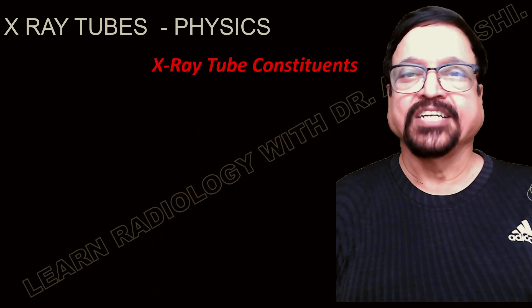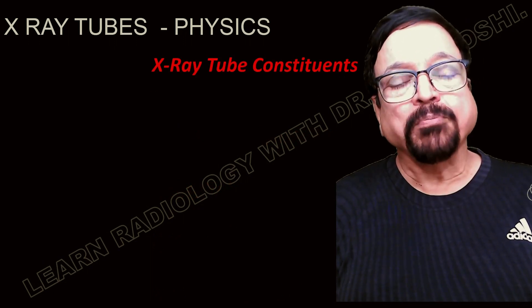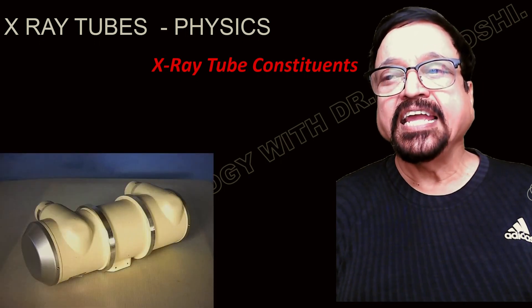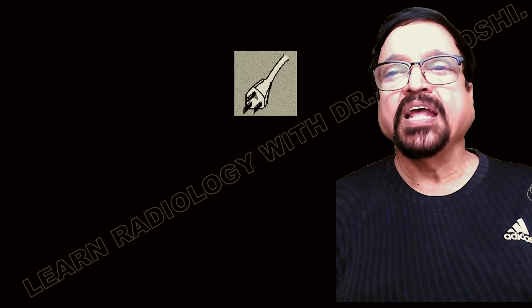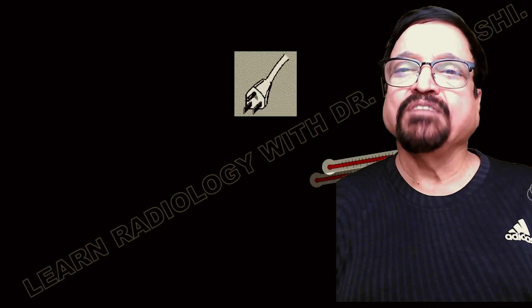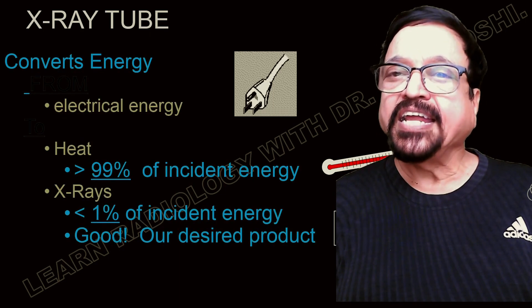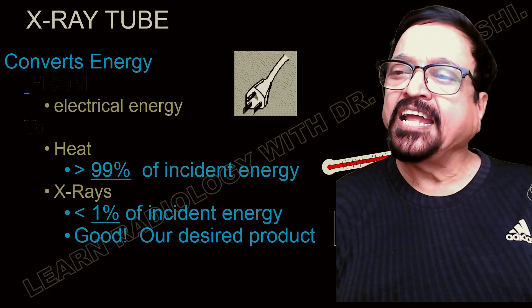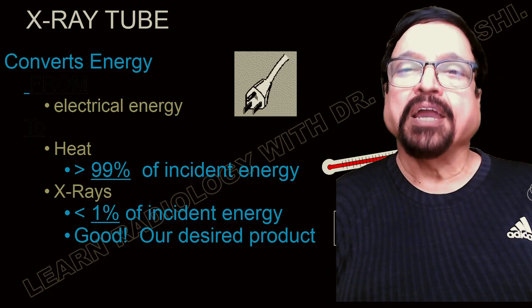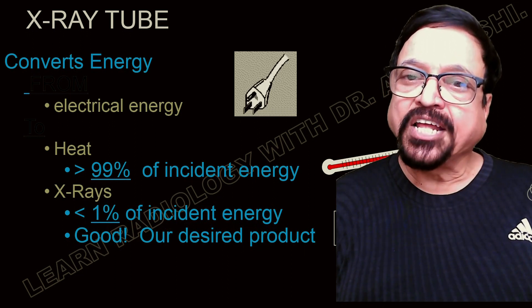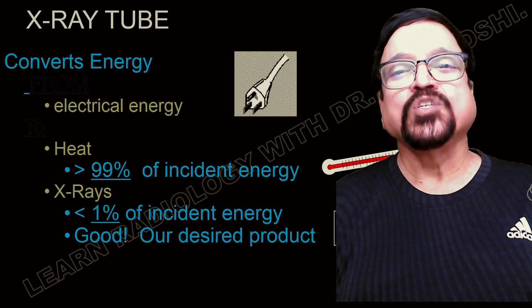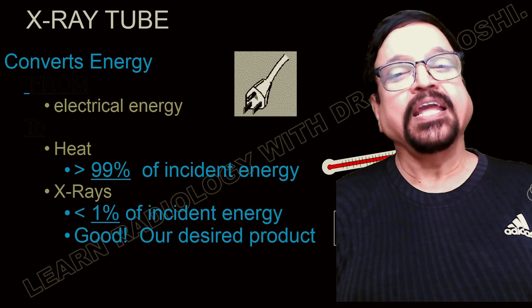Today's topic is the X-ray tube, and more particularly the anode. X-ray tubes consist of rotating anode and stationary anode types, but today's topic is only the rotating anode. What are the components of an X-ray tube? It basically converts electrical energy into radiation by using thermionic emission, then accelerating the electrons, then decelerating them, and converting them into X-rays.